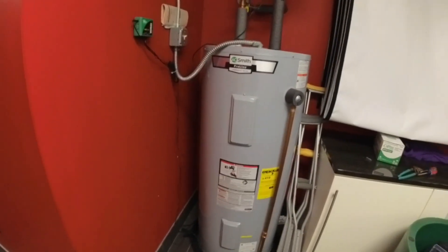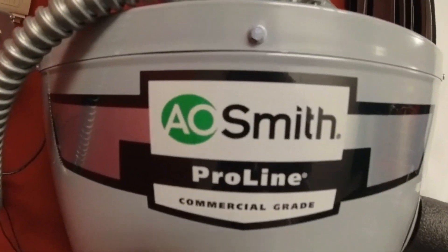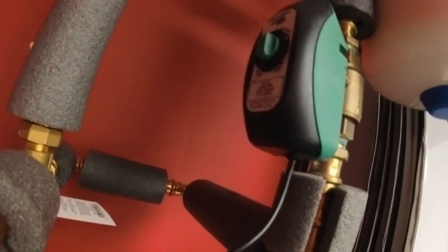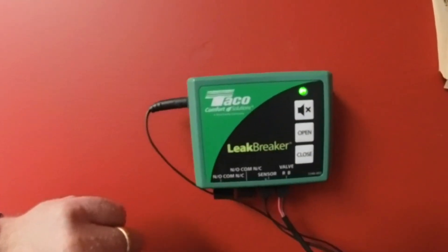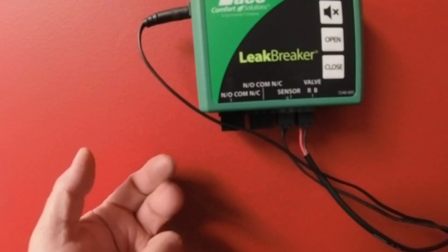Today we're going to change an anode rod on an AO Smith ProLine commercial grade water heater. It's a 52-gallon water heater. It has a Taco LeakBreaker installed with a control — it looks like one of their zone valves, but it's actually a ball valve. It's got a float sensor down in the pan, so if it detects water from a leak or overflow, it will close the valve. There's a silent alarm mode, a button to silence the alarm, open and close the valve. Your sensors plug in here, and you also have normally open and normally closed contacts, which you can use for just about anything.